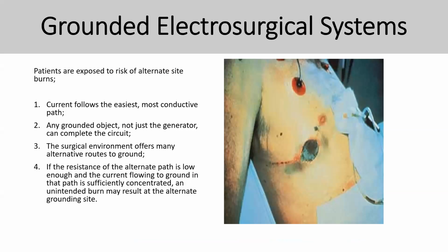So when you talk about grounded electrosurgical systems, the disadvantage is that nowadays you're not going to see much grounded electrosurgical systems. But what happens is when your electrosurgical unit is not going to perform properly, or your grounding system is not good, your radio frequency leakage is very high.